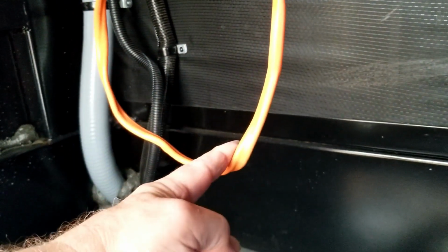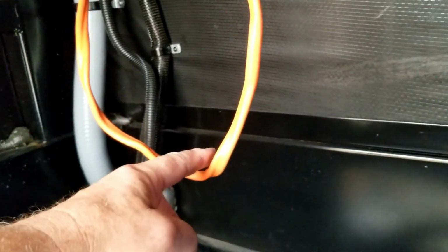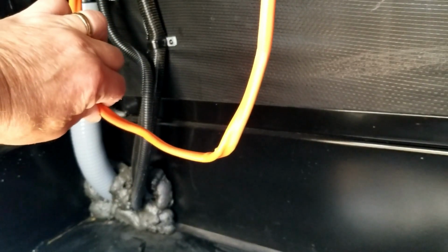Of course, I want to make sure that the power is turned off, and then I can determine which side of this wire is connected to that first 30 amp breaker and which side is connected to that second 30 amp breaker by powering the circuit back up and testing to see which one is hot. Then I'm going to take my cable cutter and cut the wire.